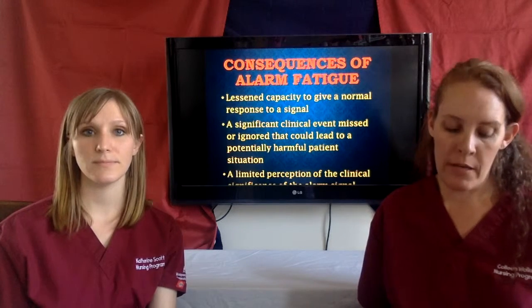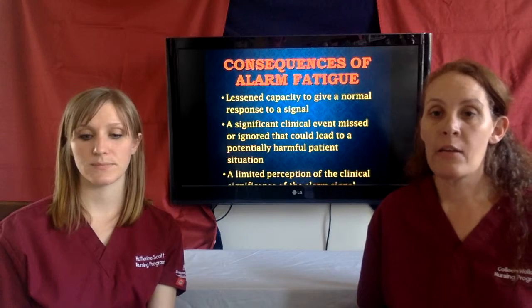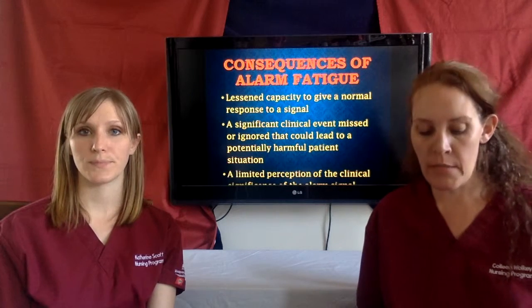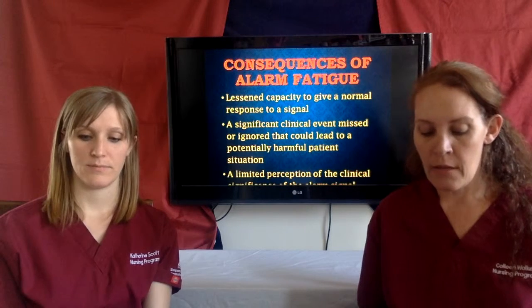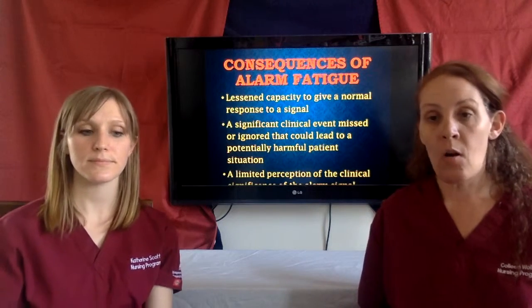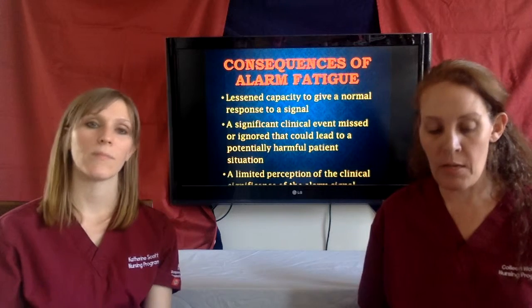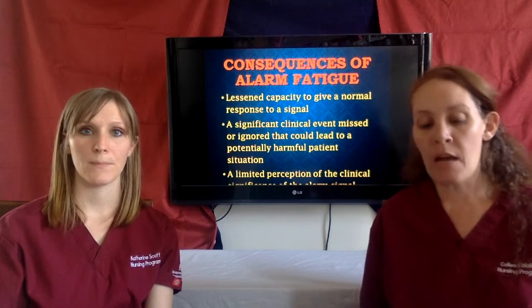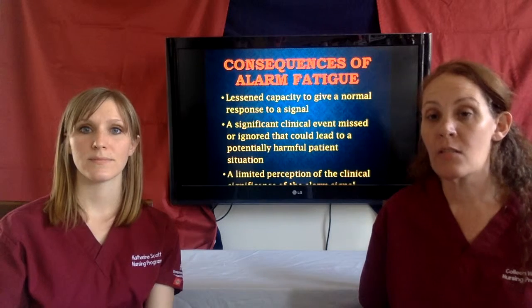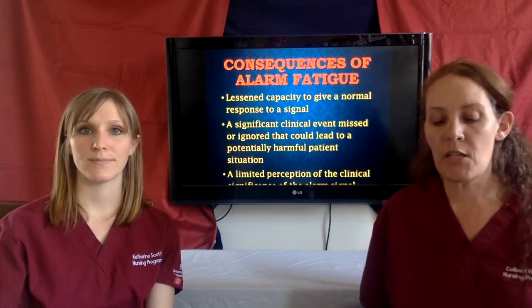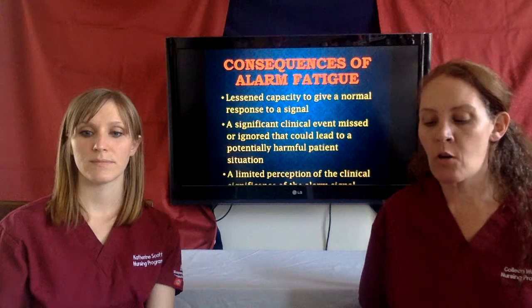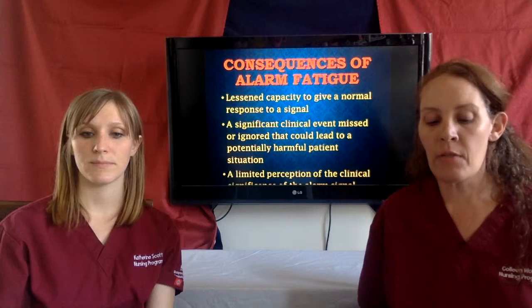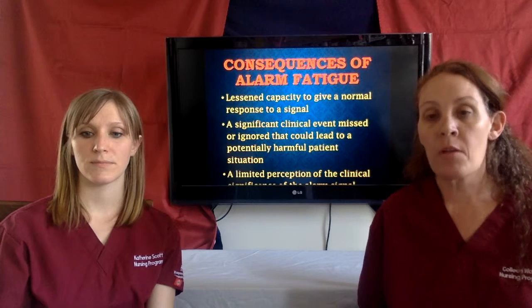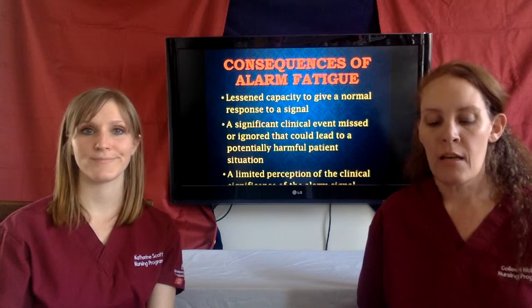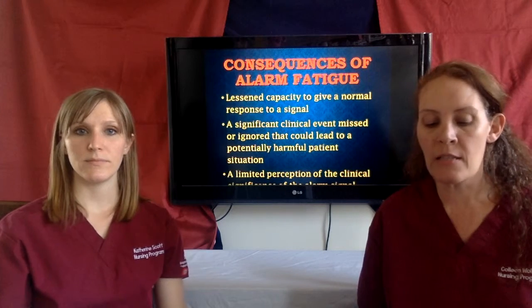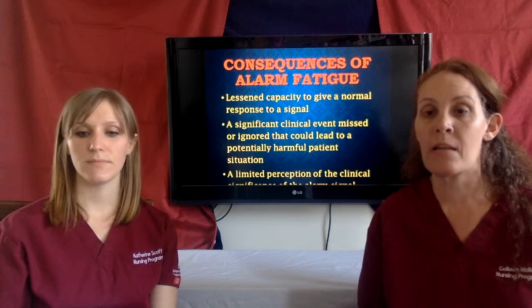Now, there are many contributing factors to alarm fatigue, and they include things such as inappropriate alarm settings, alarms being turned off, malfunction of alarm systems, and audibility of alarms not being sufficient to be heard throughout the unit. But the primary cause for alarm fatigue is nuisance or false alarms. The Joint Commission estimates that for one patient over a 24-hour period, the number of alarms can reach several hundred. Multiply that by 25 patients on the unit, and the nurses are being bombarded with thousands to tens of thousands of alarms on a daily basis.